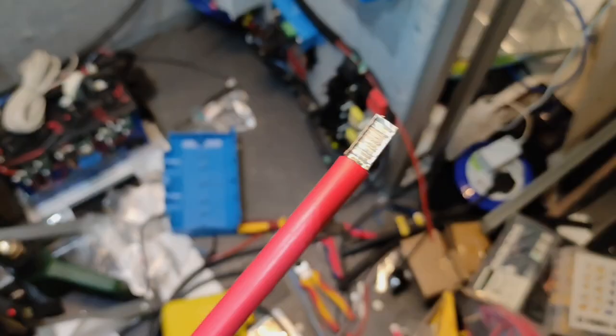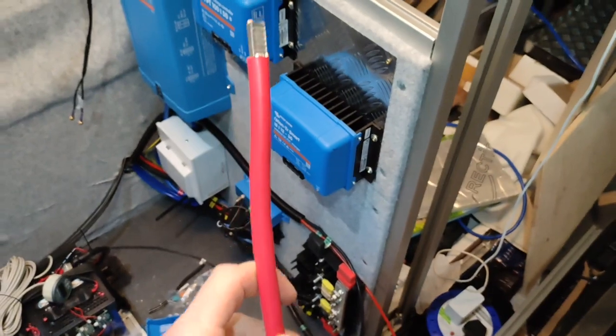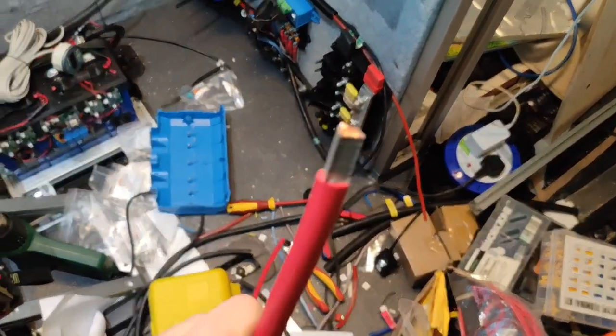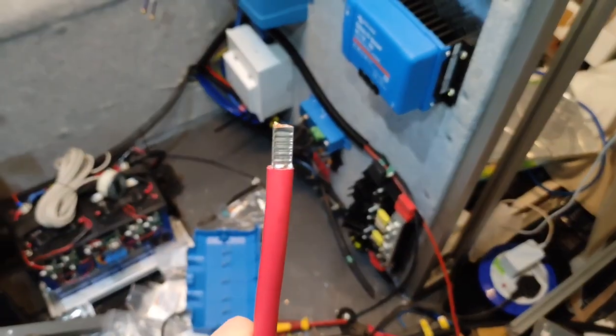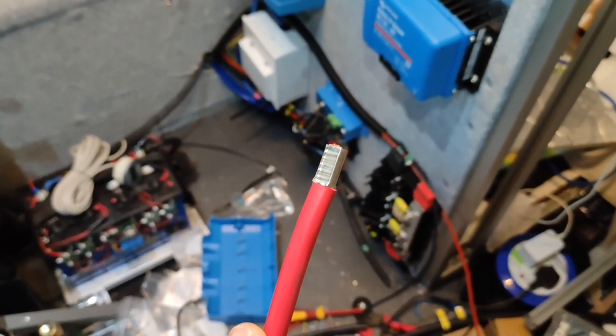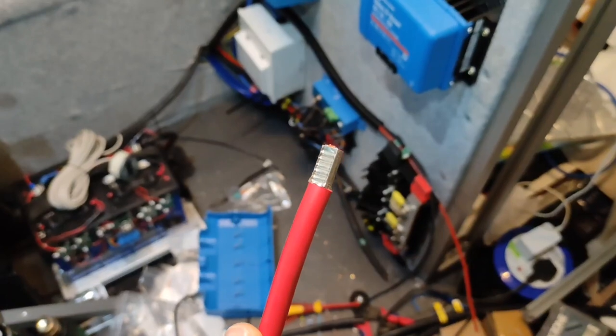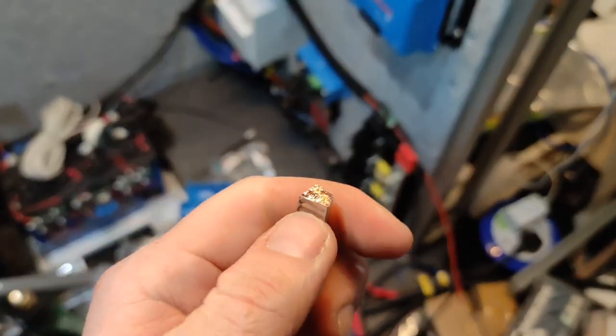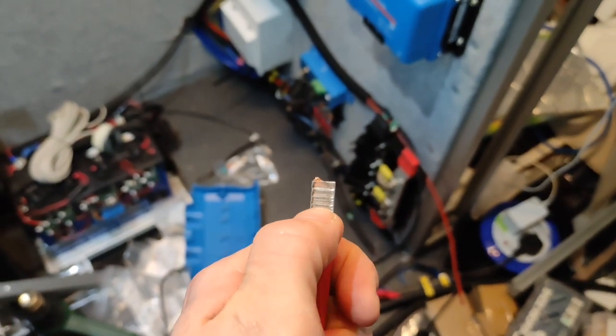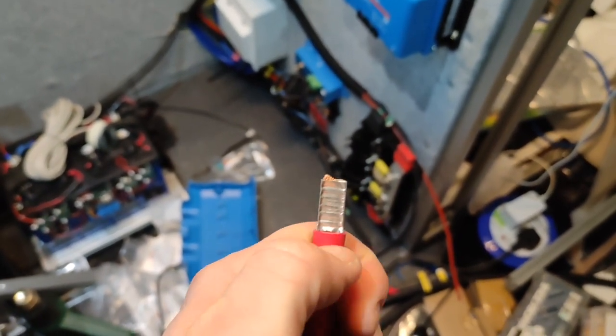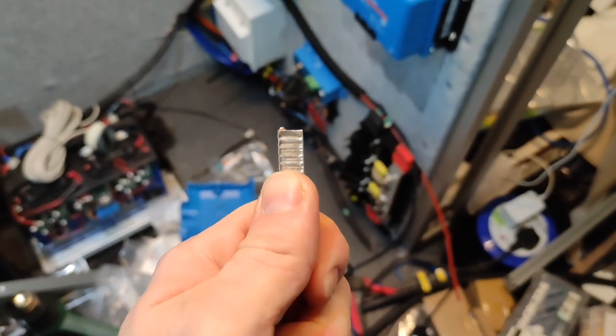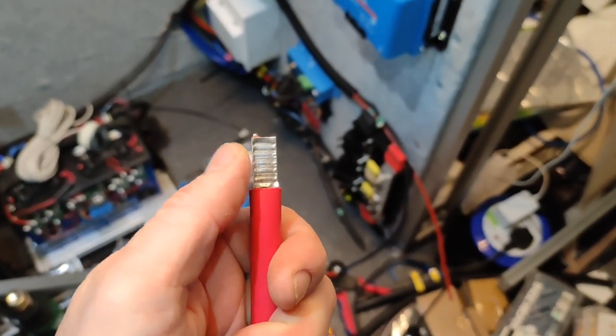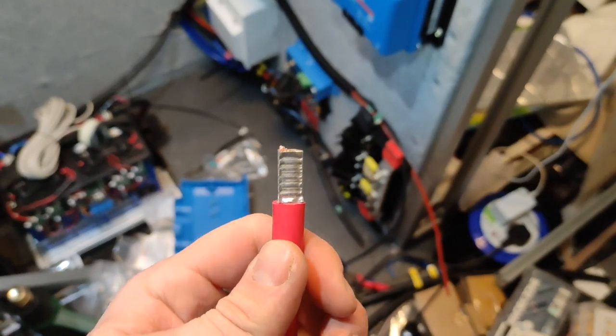So here we've got one of the feed cables for the inverter, and as you can see, we have added a ferrule to the end. And this is really important. Whenever you're using multi-core wire, use ferrules, because it means that you're keeping all of the conductors next to each other, none of them are getting loose, none of them are going to be frayed, and your screw terminals will hold onto these much, much better.